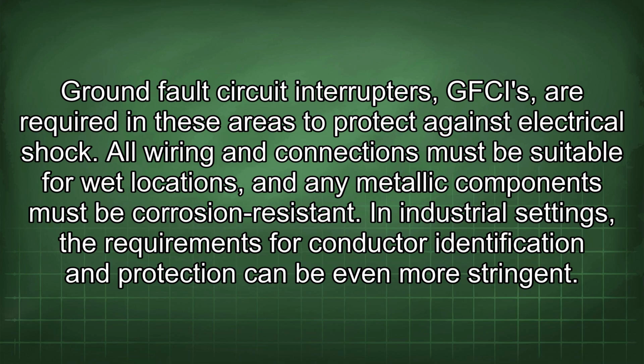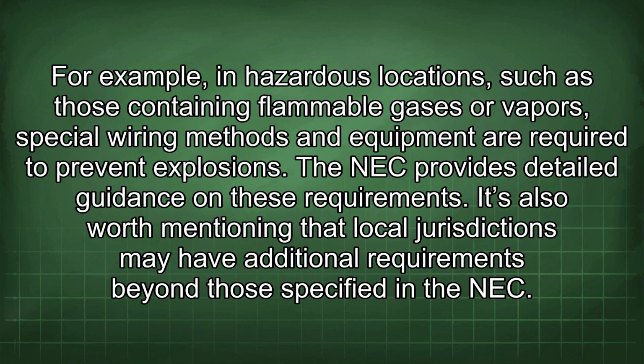In industrial settings, the requirements for conductor identification and protection can be even more stringent. For example, in hazardous locations, such as those containing flammable gases or vapors, special wiring methods and equipment are required to prevent explosions. The NEC provides detailed guidance on these requirements.